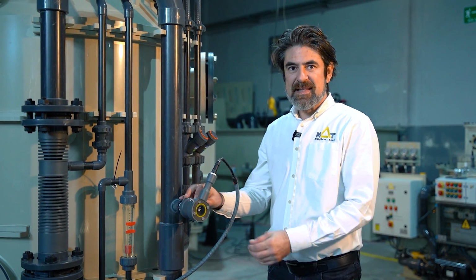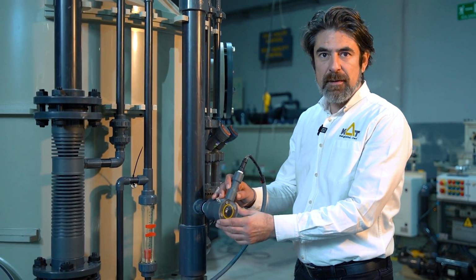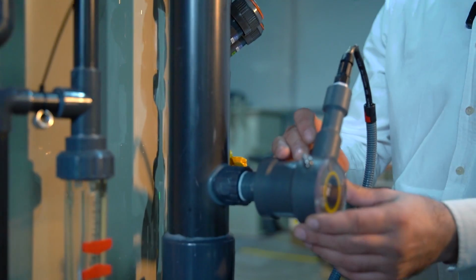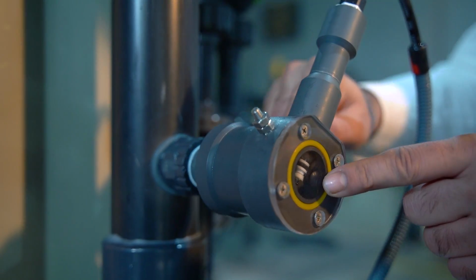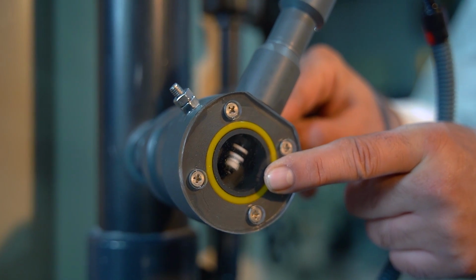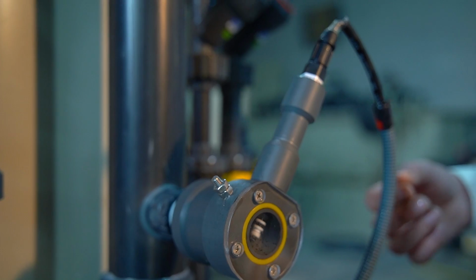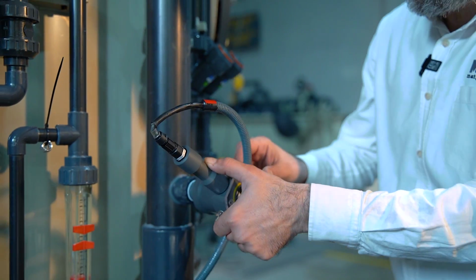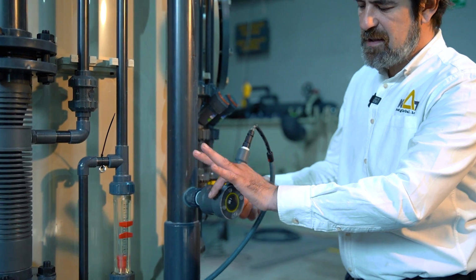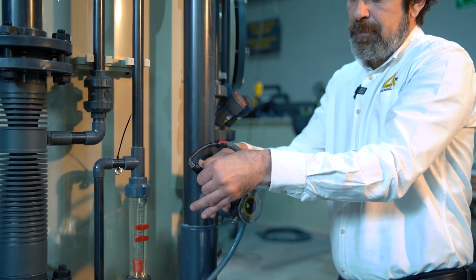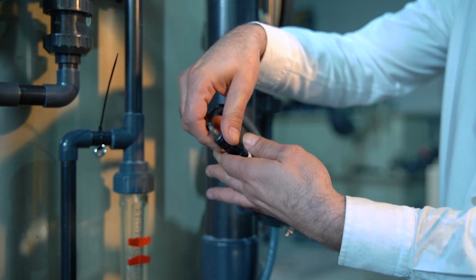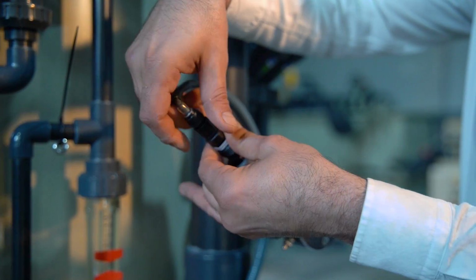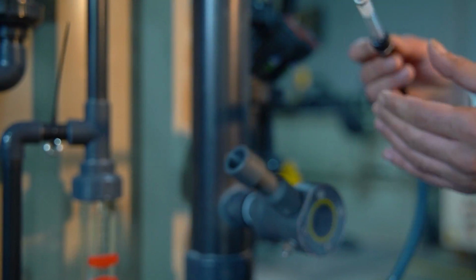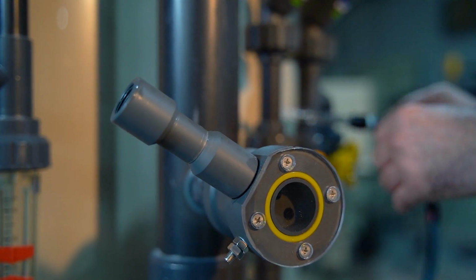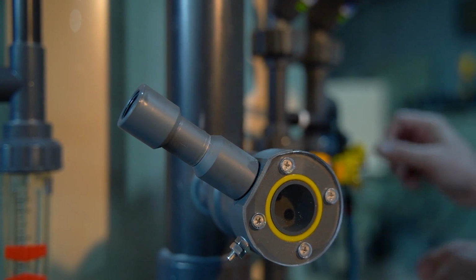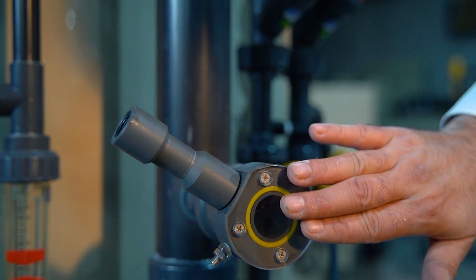Now, instead of a standard connection, we have our dry tap unit and we have water flow inside the pipe. Now we have water circulation on the probe tip. If I want to clean or replace the probe, I simply rotate it. It's very smooth and easy to rotate. Then I take out the probe. And I won't attach the probe again, to show you what will happen. Now it's in the off position.